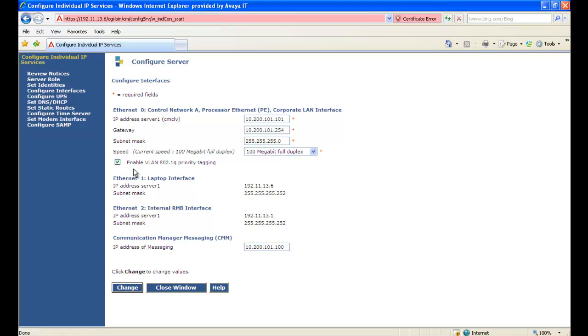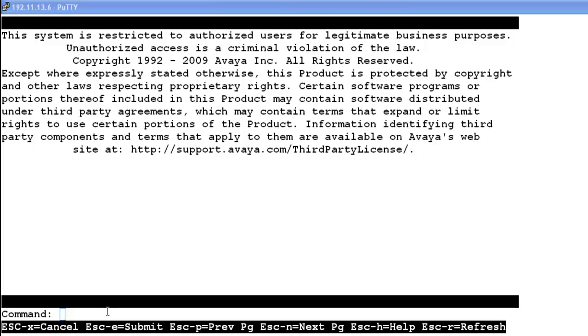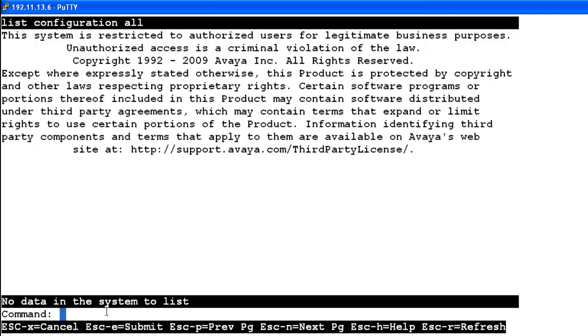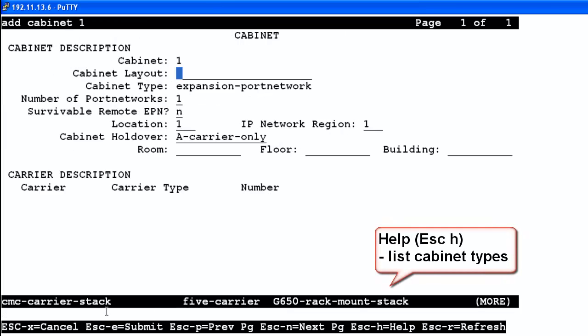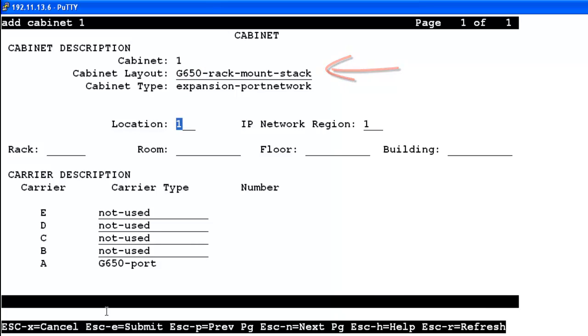We've configured the IPSI board via CLI and are now in the CM Admin pages. Running list config all shows no data in the system. We type add cabinet 1. Under Cabinet Layout we put in G650 Rack Mount Stack. Our location is 1 in IP Network Region 1, and we're only using Carrier A. We save this configuration.